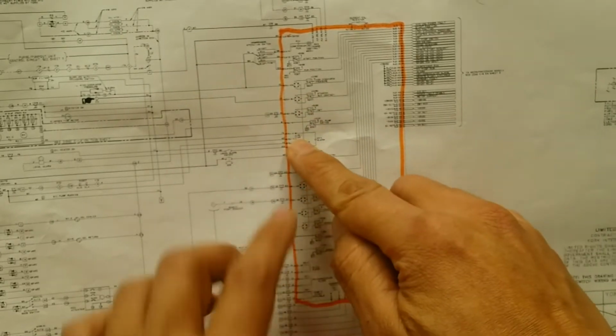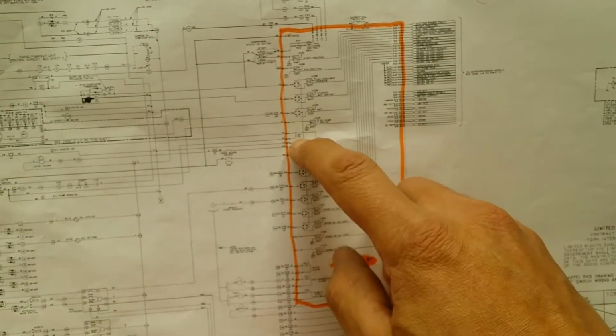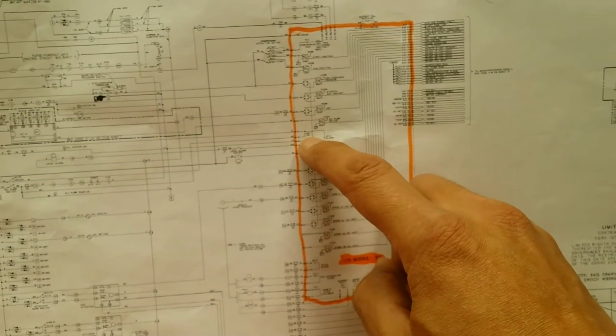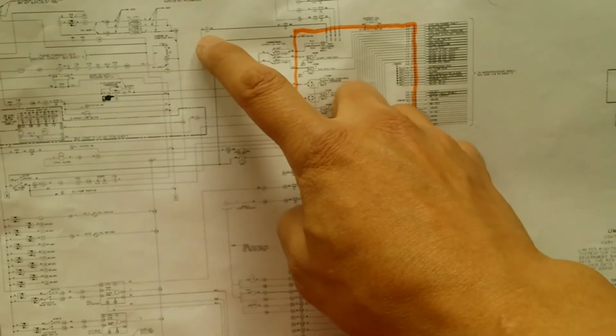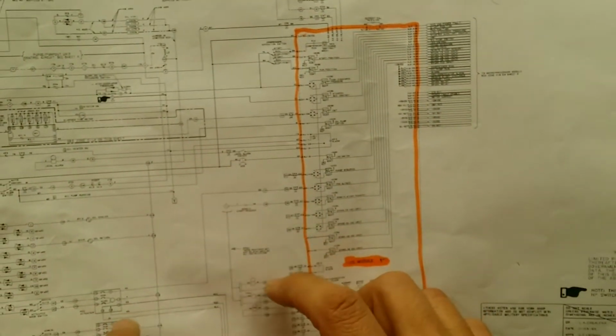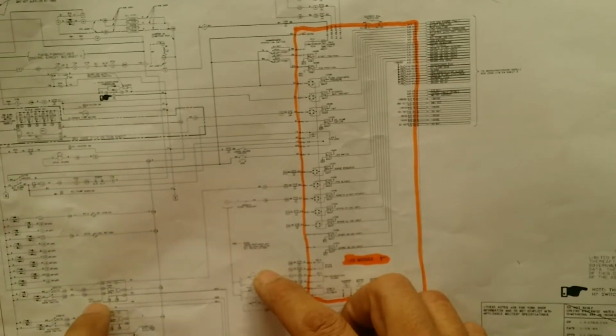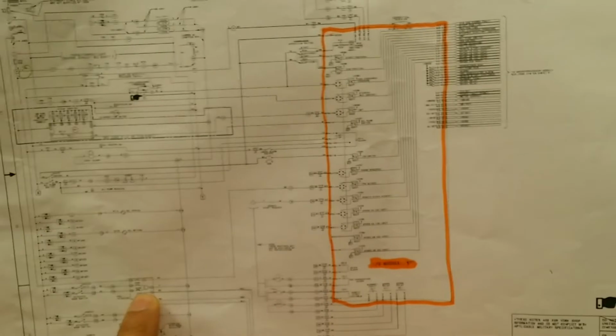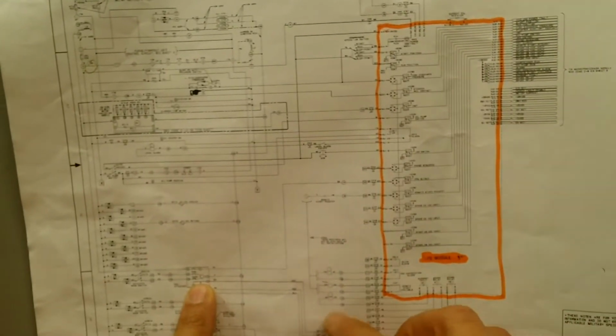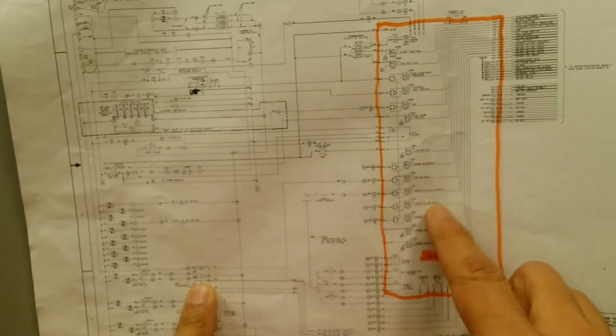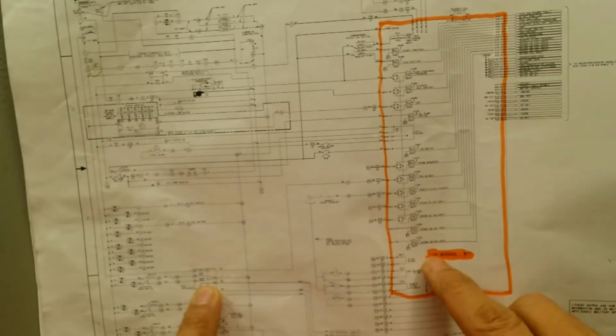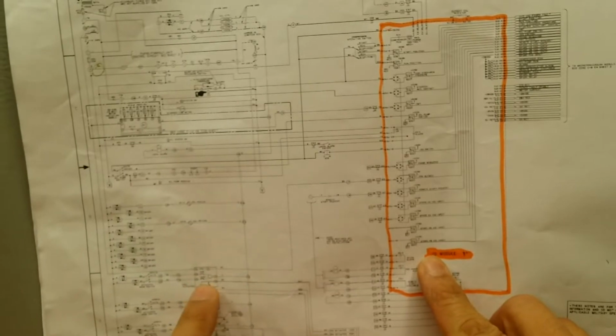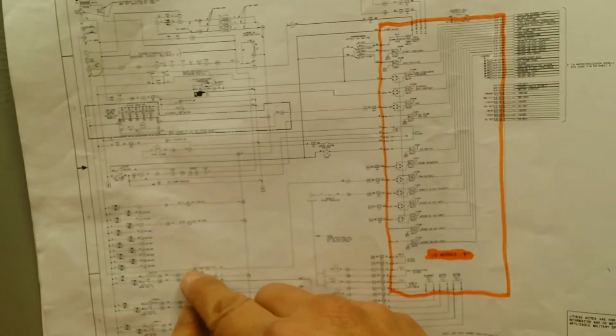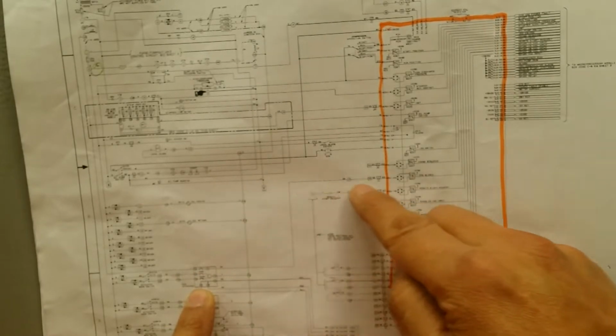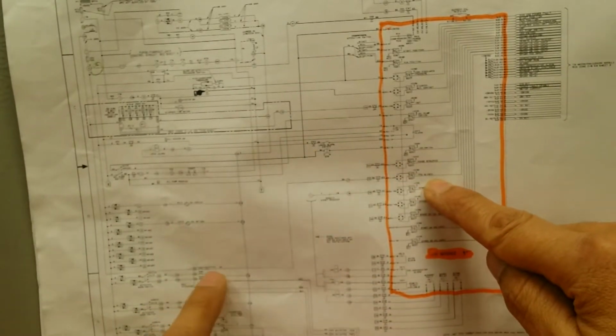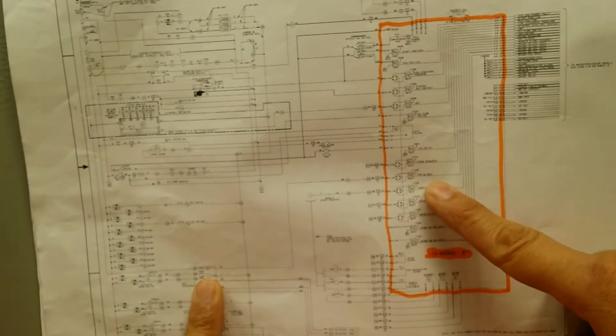Additionally, this card starts your oil pump via K2, and via K1 starts your compressor. Very important over here is the PRV valve. When the system is energized, the circuit card, not the circuit card, the other one, the microprocessor module, will command the SSR closed so that this valve is closed. Then there is this switch over here that has to be closed so that the circuit card, this one over here, can verify that this valve is closed. That's one permissive to be able to start the AC.